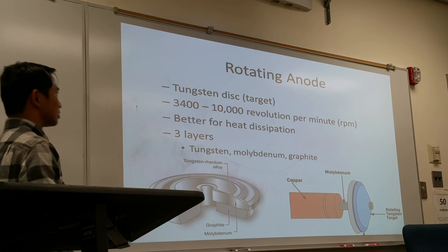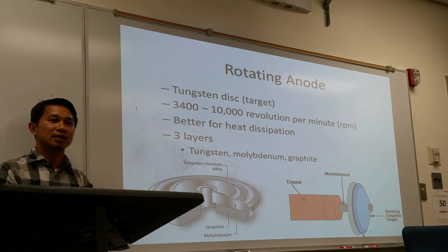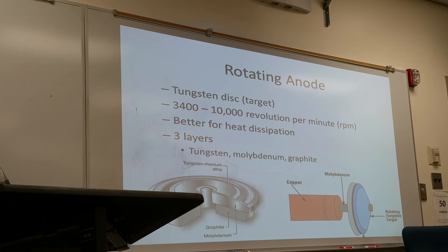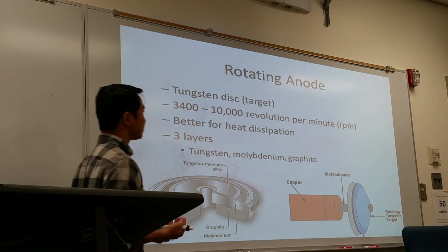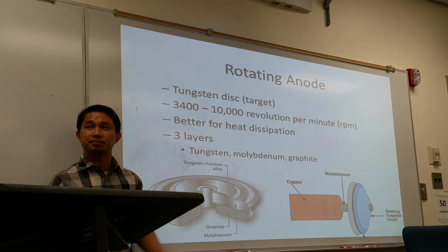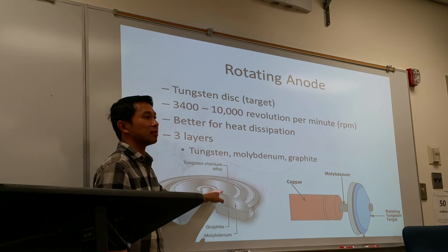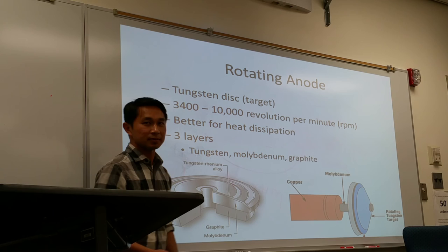The rotating anode is made of tungsten — we call it the tungsten disk or target, because that's where the electrons strike. The rotating disk can revolve at 3,400 to 10,000 revolutions per minute. The advantage of the rotating anode is that heat dissipates over a different surface area each rotation. The layers of the rotating anode from top to bottom are: tungsten on top (where x-ray production occurs), supported by molybdenum, then graphite, then supported by a column. The tungsten is also mixed with other alloys, such as a tungsten-rhenium alloy.